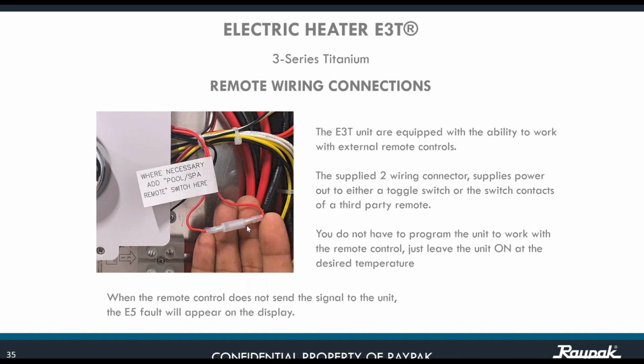Simply like that. So when the remote control does not send any signal to the unit, an E5 fault is going to appear on the display. It's not a fault, it's simply that it's not closing the circuit. Right here, if you see this jumper, basically that is the voltage. But if this voltage is getting interrupted because at that particular point the temperature sensor of the automation system is not seeing a need for a call for heat, well, no signal is going to be coming from the automation system. Nothing is going to happen. E5 is going to appear on the display.